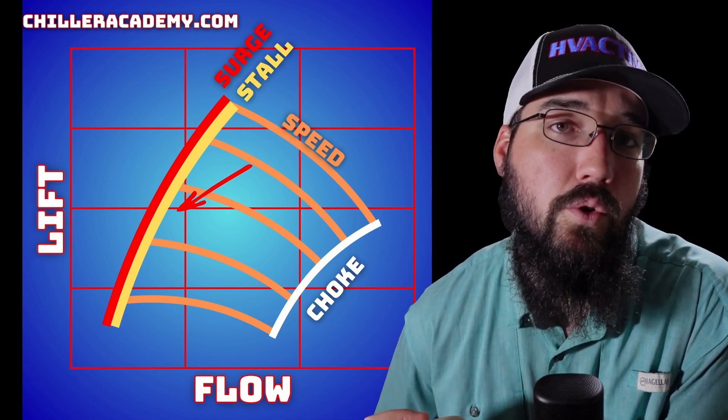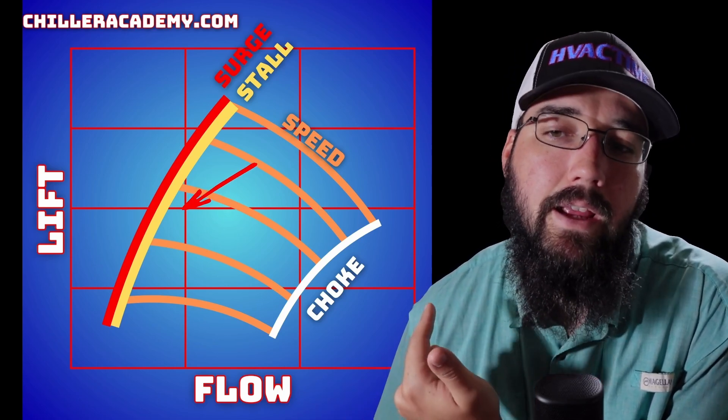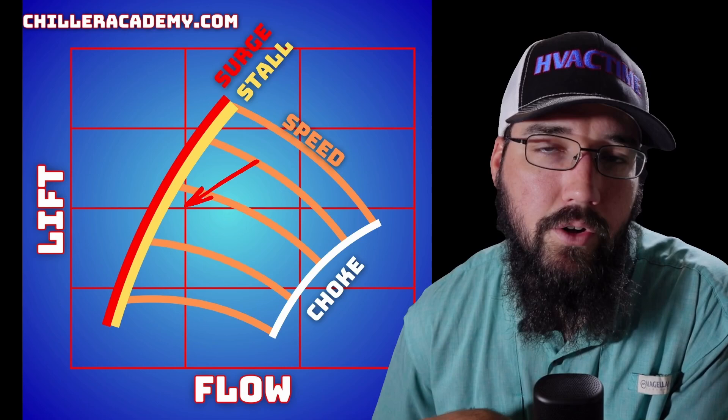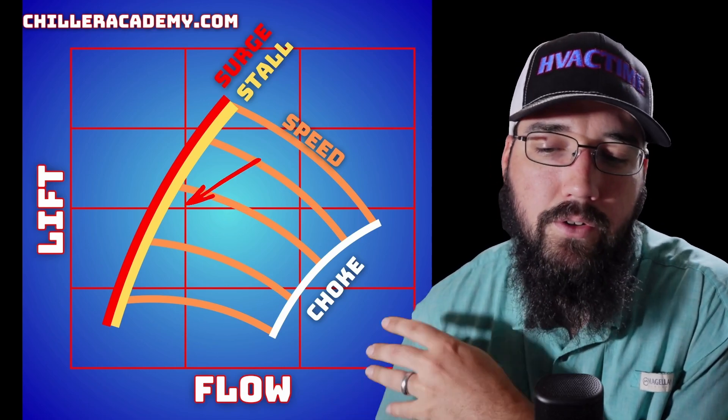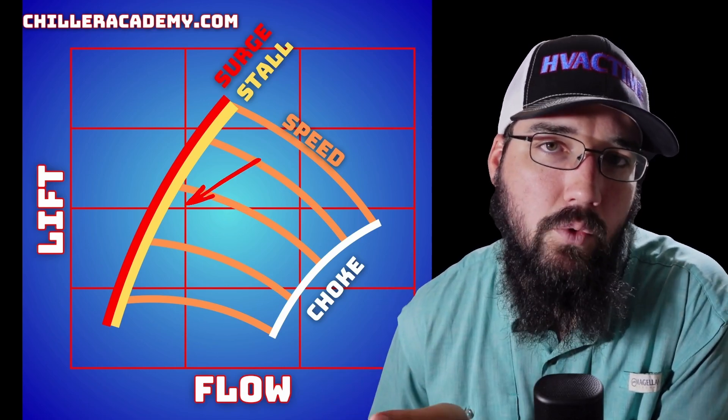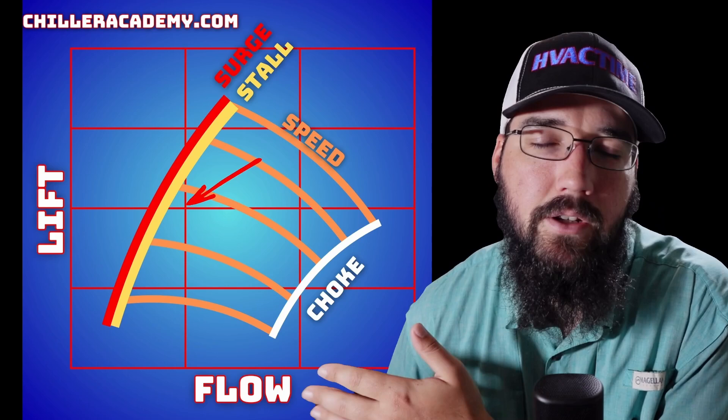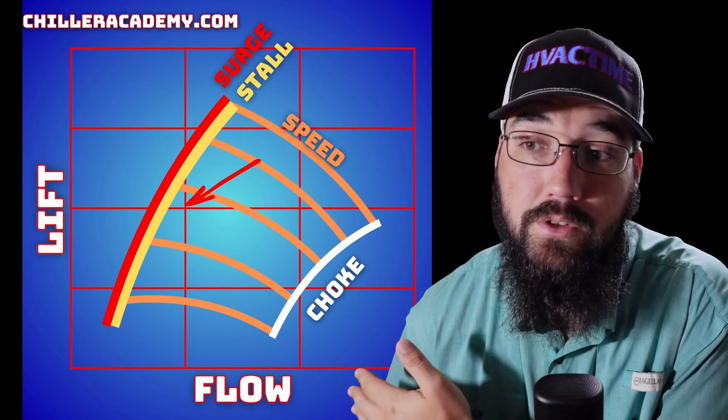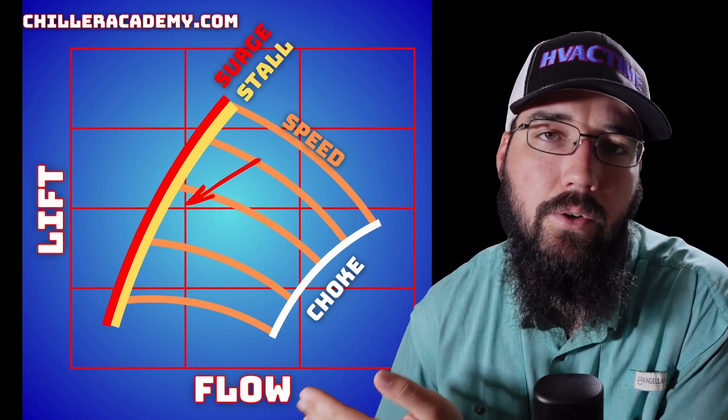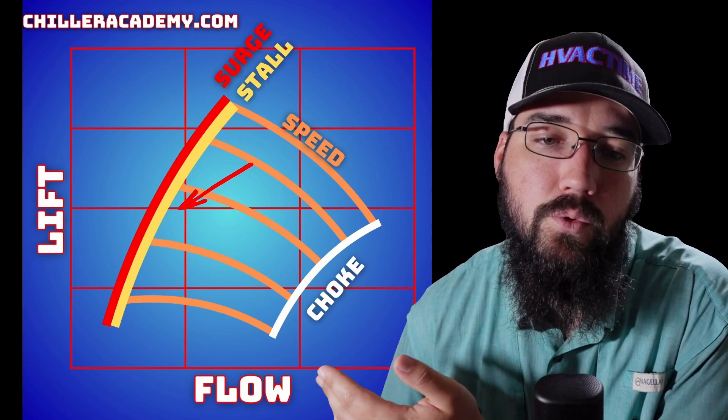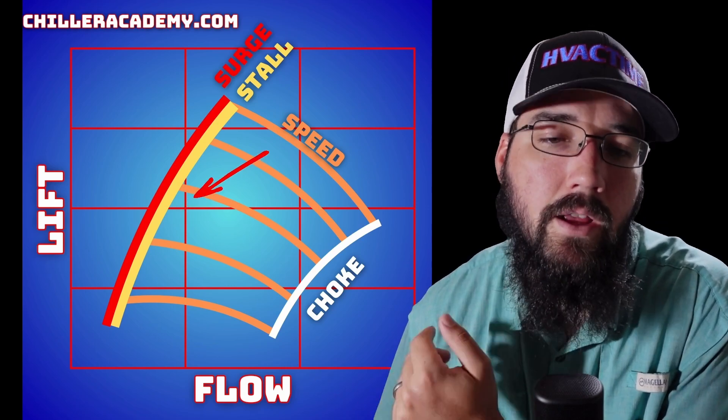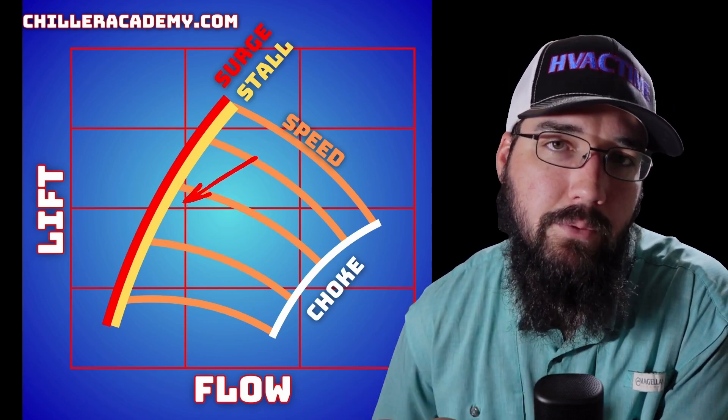Or the leaving water, I should say—all this is about leaving water. If we over-cool the leaving water, that's not good either, and we end up pushing ourselves into our shutdowns, which we don't want this thing to shut down for any reason, whether it be for surge or for overshooting our set point. We have this balance that we have to get into at that point.